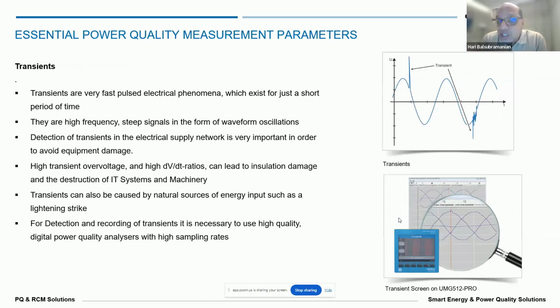Transients is the next topic, which usually happens within a cycle. Within a sine wave cycle or within a half cycle of 10 milliseconds, the transients can be oscillatory, or they can reach a peak and then reduce. Both these kinds of transients are not good for the systems, because the insulation gets weaker when these kinds of transients happen.